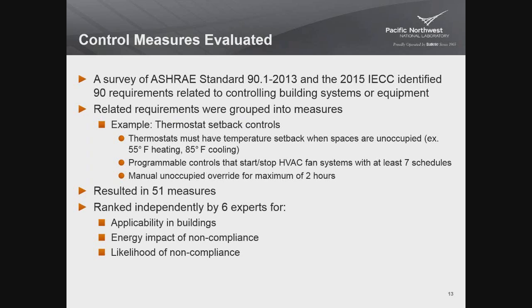That includes 3 requirements. There's a requirement that says when a building is unoccupied, the temperatures need to be set back. And it actually says in one of those 2 codes, I can't remember, 55 degrees for heating and 85 degrees for cooling. So 30-degree offset between heating and cooling when people are not in the building. There's also a requirement that says you have to have programmable controls with start-stop functions with at least 7 different available schedules for each day of the week.